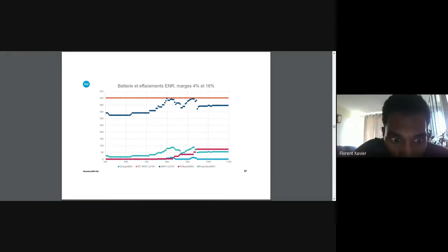And you can see that if we have an increase of production, we can see the increase of current on the line. It's in blue color at the top. And when we reach the 440 ampere value, our algorithm works in order to absorb the energy by the storage capacity and to reduce the power on the line. And this is the way that these batteries work to solve congestion issues.